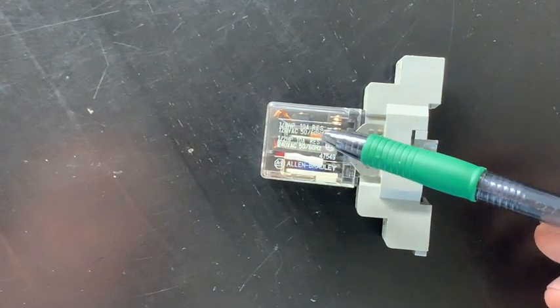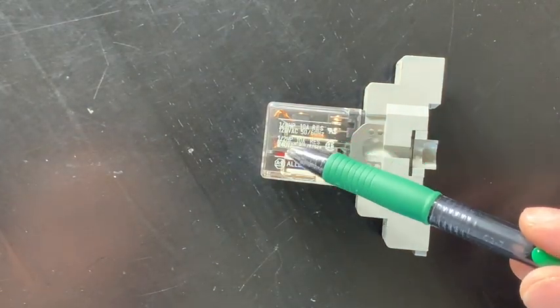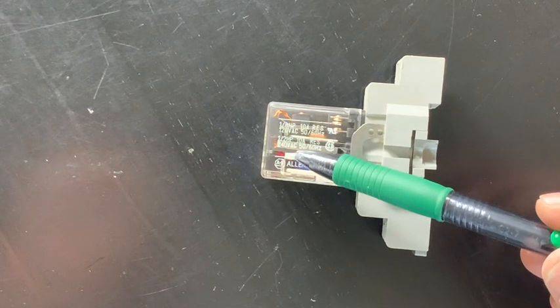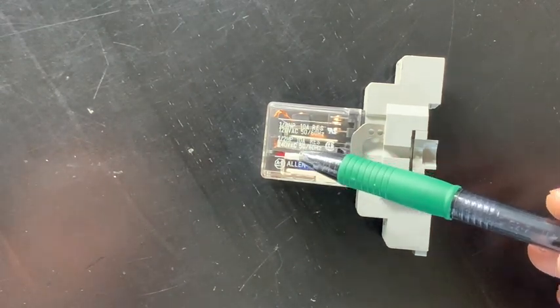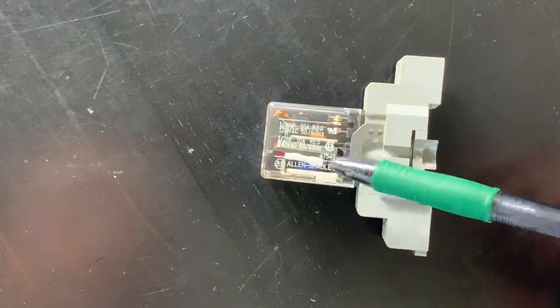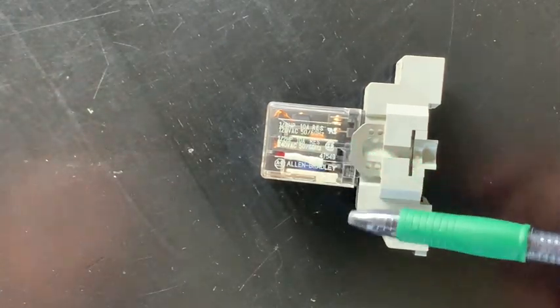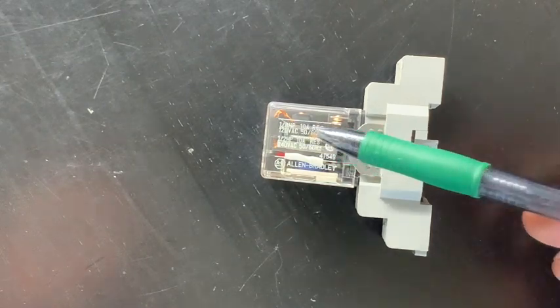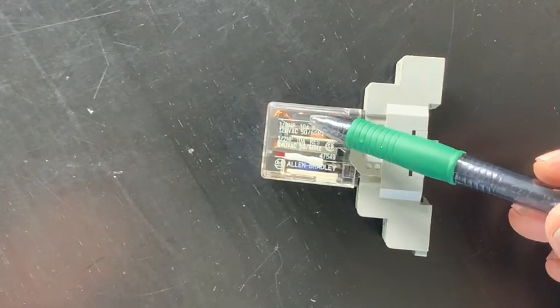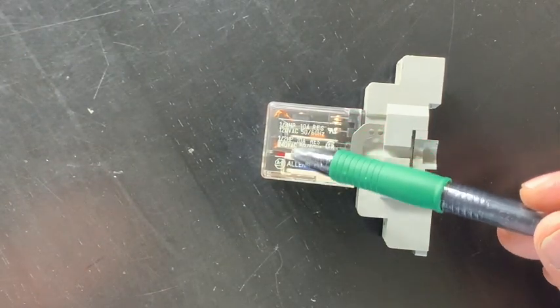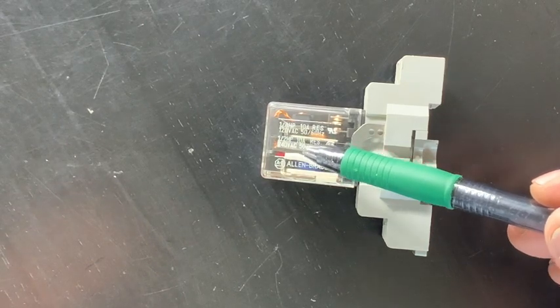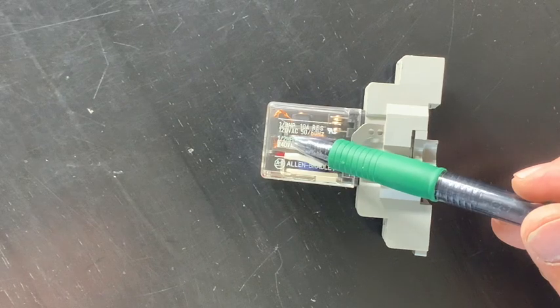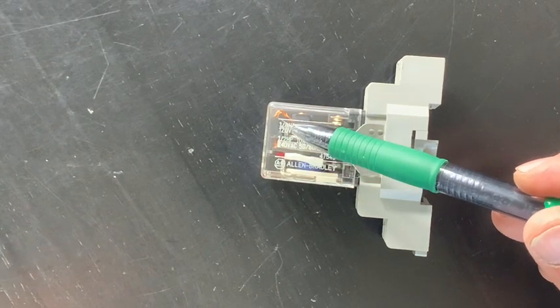Here it says 10 amps, third horsepower, 10 amps 120 volts AC, half horsepower at 240 volts, 10 amps AC. So a third horsepower at 120 volts is going to pull close around that. And then a half horsepower at 240 volts, even though half horsepower is larger than a third horsepower, since you're running it at higher voltage 240 volts you're not going to pull more amps.